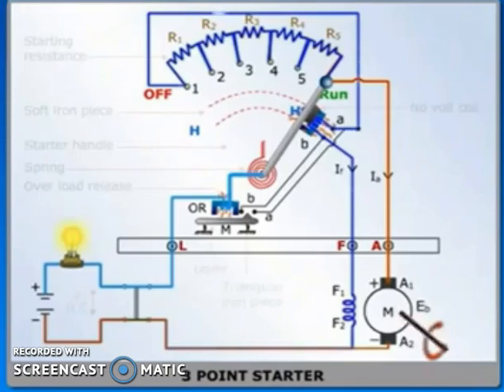Next, the field current flowing through the HC coil produces a force of attraction greater than the spring pull. In view of this, the handle H is held in the run position, and the entire starting resistance is cut off. The holding magnet or coil HC is also called no-volt release.